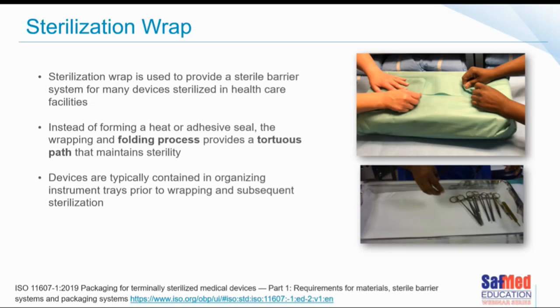Sterilization wrap is used to provide a sterile barrier system for many devices sterilized in healthcare facilities. Instead of forming a heat or adhesive seal, the wrapping and folding process provides a tortuous path that maintains sterility. Devices are typically contained in organizing instrument trays prior to wrapping and subsequent sterilization. That tortuous path — the folding — matters. It is stated right at the beginning of the standard: it is a critical endeavor, and how we do this really and truly does matter.